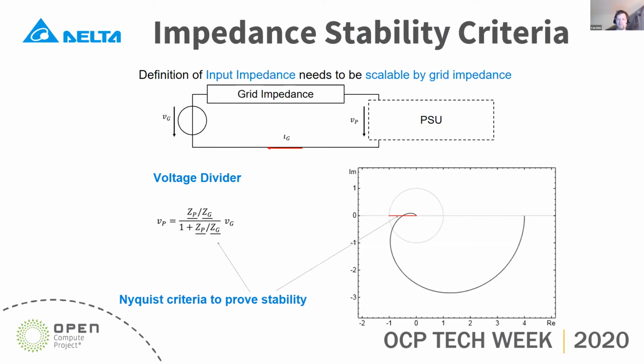Now we come to the main point of this presentation, related to impedance stability modeling. If you assume the power supply is operating with a grid impedance as shown in the top schematic, doing a simple voltage divider calculation, you look for the ratio between the impedance of the power supply and the impedance of the grid. Applying the Nyquist criteria, the real part of this ratio in complex numbers should never exceed -1, because then the denominator becomes 0 and we have an unstable point. This is basically the Nyquist criteria used to prove the stability of the system.